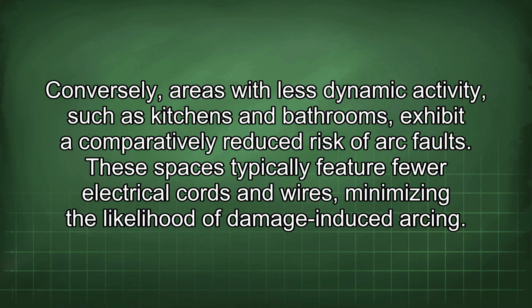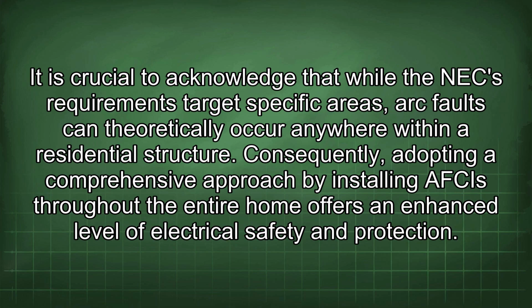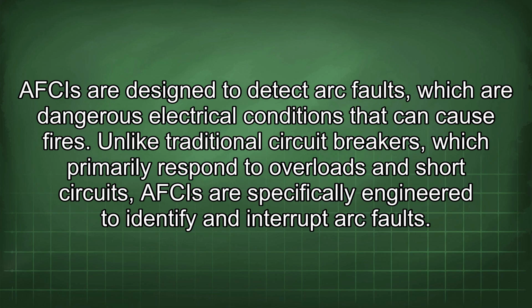Conversely, areas with less dynamic activity, such as kitchens and bathrooms, exhibit a comparatively reduced risk of arc faults. These spaces typically feature fewer electrical cords and wires, minimizing the likelihood of damage-induced arcing. It is crucial to acknowledge that while the NEC requirements target specific areas, arc faults can theoretically occur anywhere within a residential structure. Consequently, adopting a comprehensive approach by installing AFCIs throughout the entire home offers an enhanced level of electrical safety and protection. AFCIs are designed to detect arc faults, which are dangerous electrical conditions that can cause fires.